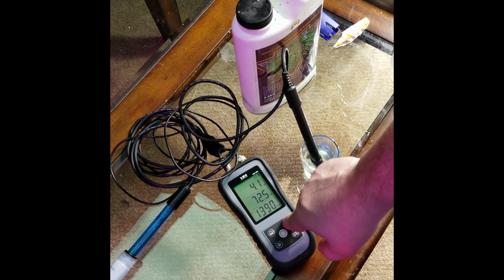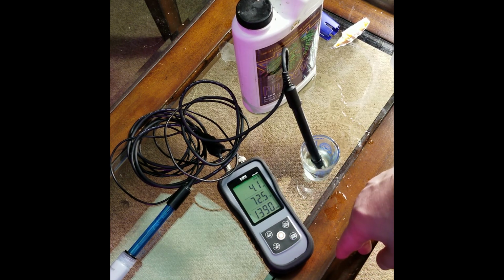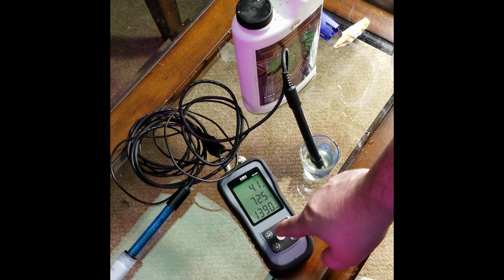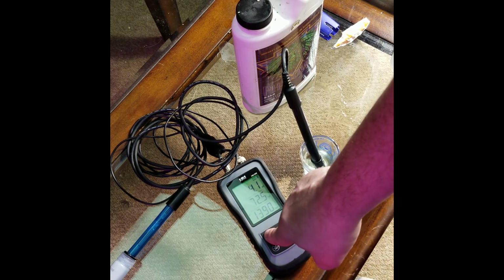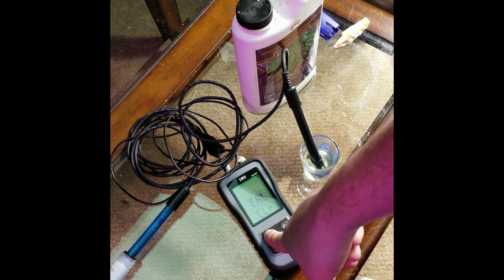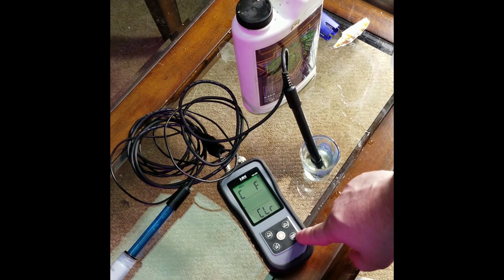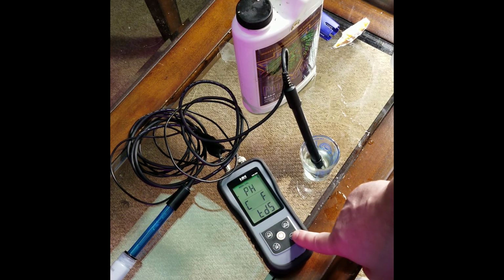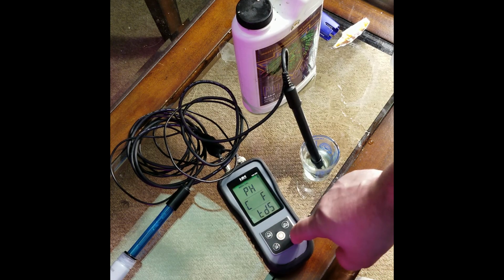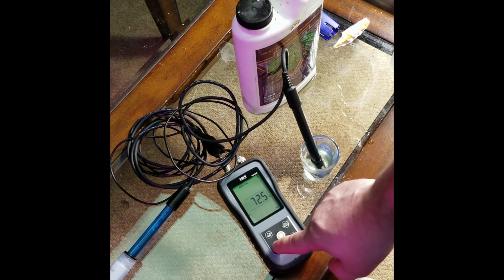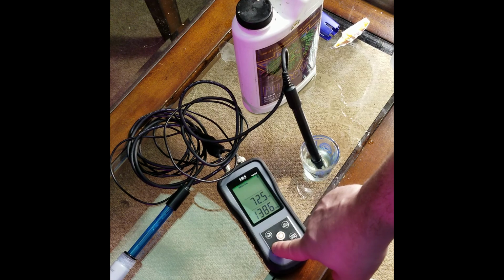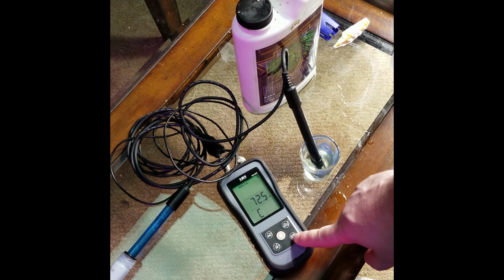Alright. So we spilled, so we're going to try this again. I did actually calibrate it. Didn't realize it wasn't filming. So we're just going to do it again because I do tend to do it more than once. We hit and hold menu. We go 1 down to calibration. Hit our enter key. 2 down to TDS. Hit the enter key. And then we do our down arrow till we're at 1385. Hit the enter again.